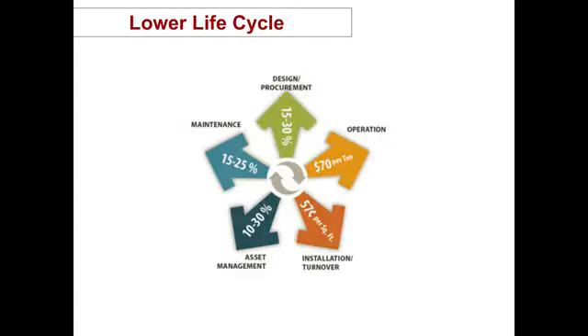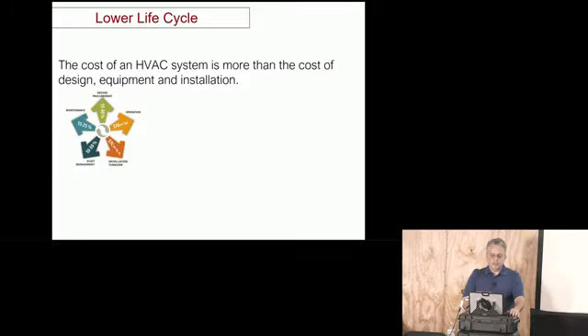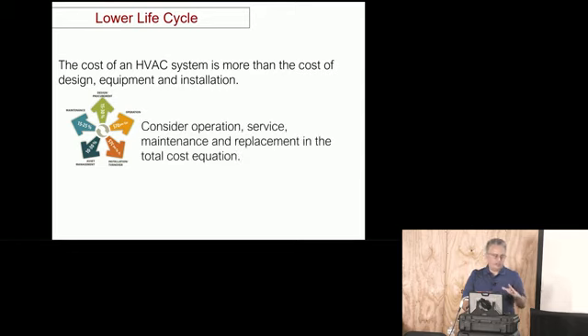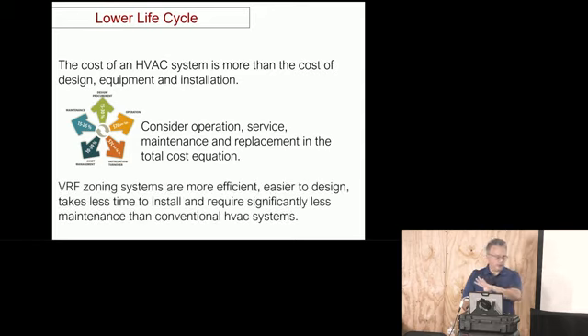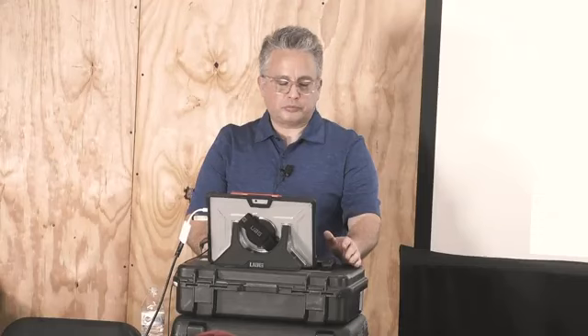So life cycle costs are much more favorably achieved with VRF. Why? The cost of an HVAC system is more than just the cost of design, equipment, and installation. You've got to consider the operation, the service, the maintenance, and replacement as part of the total cost. VRF zone systems are more efficient, easier to design, take less time to install, and require less maintenance. And in our service and maintenance section, you'll see why.